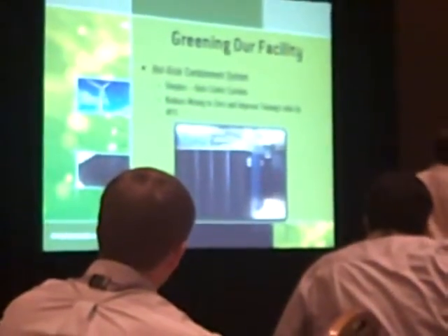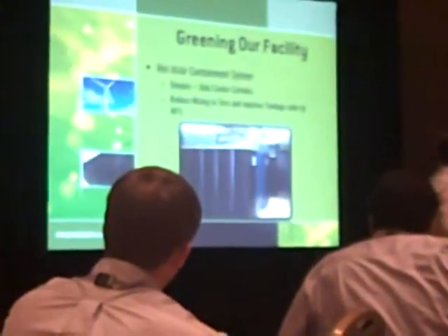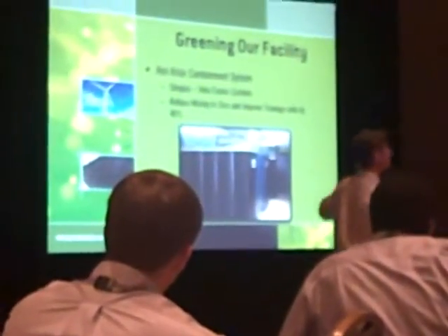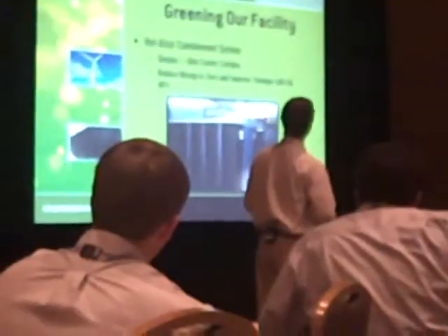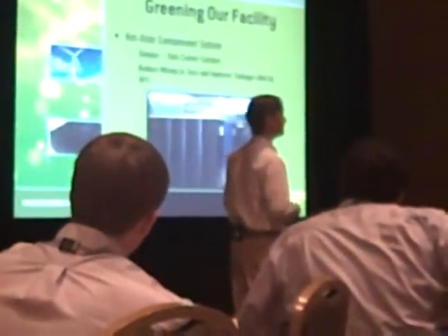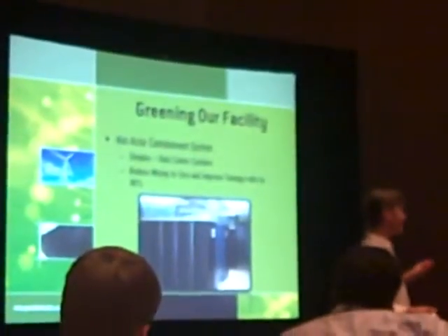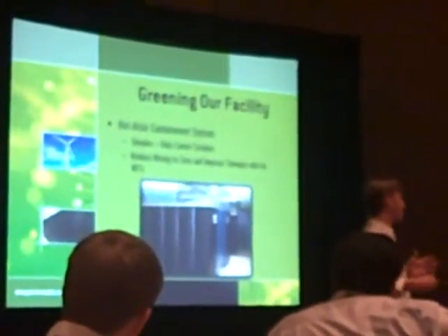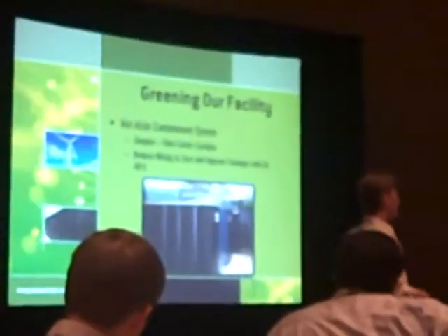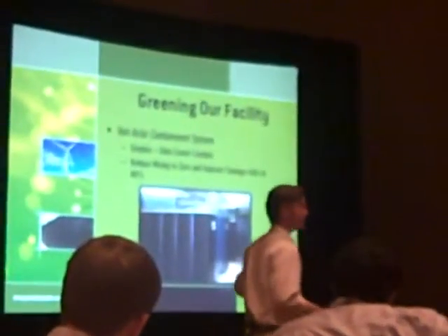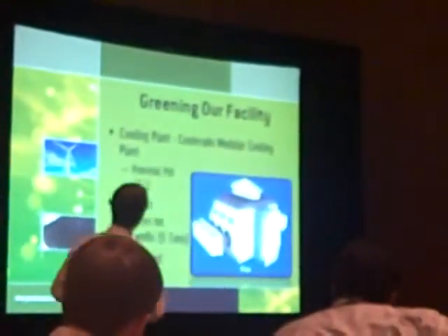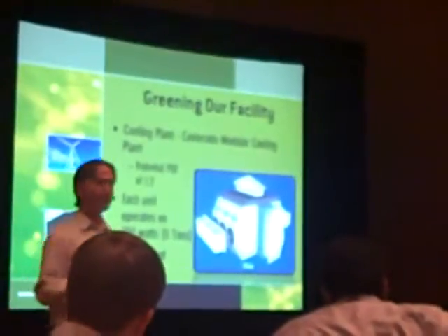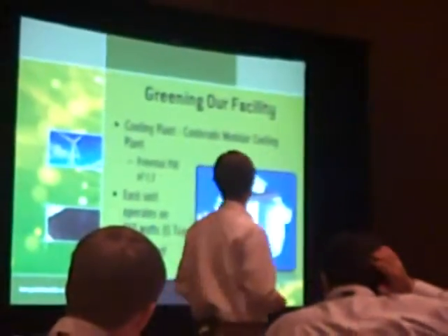We basically run a cold data center with hot aisles, basically. And then everything above the ceiling tiles is a hot plenum. So the challenge for us actually in our cooling system is not how to use the outside ambient air to make sure it stays cold enough. What happens when it's 10 below or 0 in our data center? And so we'll kind of talk about that next. And it's probably a completely different challenge than most of you are faced with.